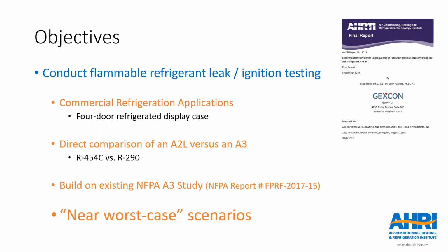This study built upon an existing body of work previously performed by the NFPA in 2017 with ignition testing of propane. It's important to note that what we're looking at here are near worst case scenarios, where we're trying to create the conditions to force an ignition to occur, see what happens, learn from that, and report that back into the standard development process. That's really our main goal: to help inform the standards. Next slide, please.